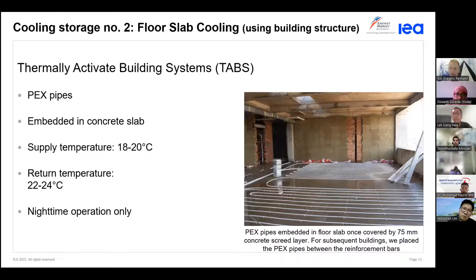This runs at night only. Just like the phase change material tank, we cool down the slabs to about 21 degrees at night, and that cooling is released passively during the daytime - or rather the slabs absorb heat in the building. So when people enter, when sunlight enters, when heat from lighting and printers goes into the space, it's absorbed into this big thermal mass, and the floor slab temperature increases about 1 degree during the day, then come nighttime we cool it down again by 1 degree. So it's actually a very stable system.